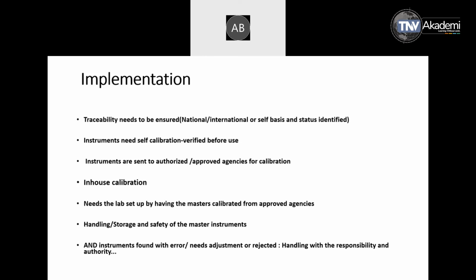Many inspection organizations fail to do that, and sometimes those errors increase, and items unnecessarily get accepted, reworked or rejected. See, if rejection or rework is really warranted, then it is all right. It should not be rejected or accepted because of the error in the instrument. Some instruments need adjustment also. They can be fine-tuned, they can be adjusted, and the readings can be brought under control. And sometimes they really go out of total control, and they go to rework, or sometimes they are rejected. So who is authorized to adjust, who is authorized to readjust, or who is authorized to reject the instruments or machine, because they are all costly? A wrong decision should not be taken.